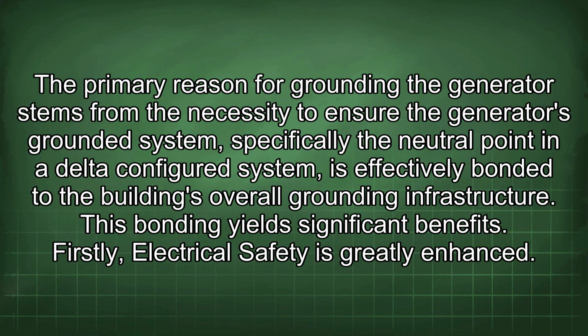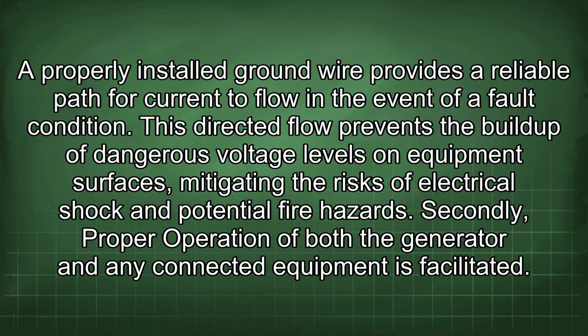The primary reason for grounding the generator stems from the necessity to ensure the generator's grounded system, specifically the neutral point in a delta-configured system, is effectively bonded to the building's overall grounding infrastructure. This bonding yields significant benefits. Firstly, electrical safety is greatly enhanced. A properly installed ground wire provides a reliable path for current to flow in the event of a fault condition.